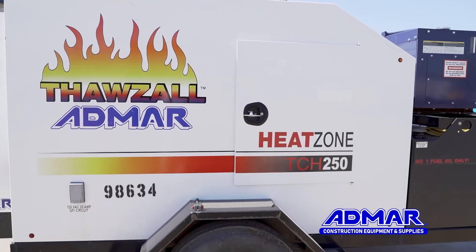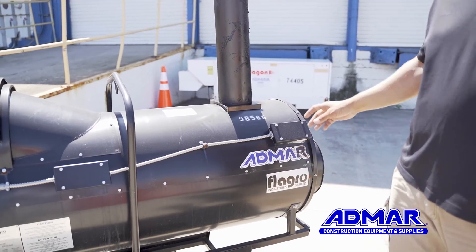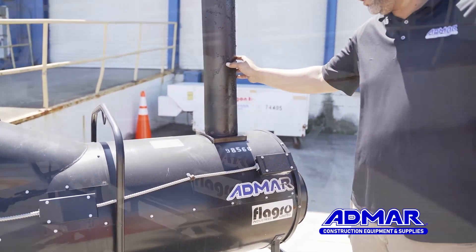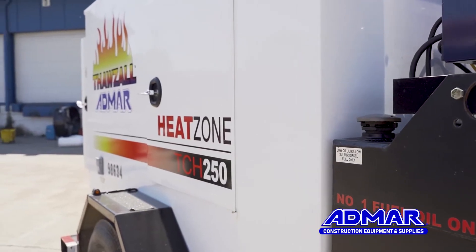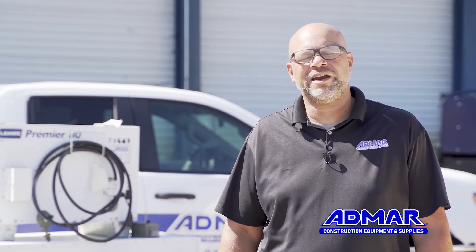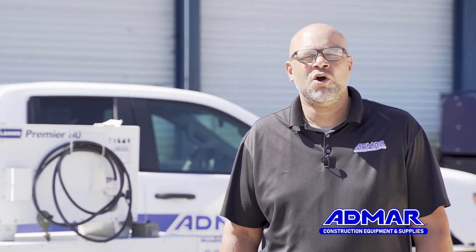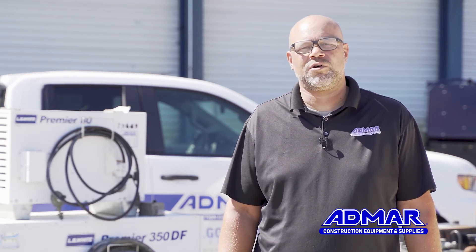The next type of heater we would like to discuss is the indirect fired heater. An indirect fired heater is similar to your home furnace. Temperature rise is achieved through the heat exchanger, and then this warm, clean, dry air is circulated into the project through a series of heating ducts. Although the indirect design lacks the 100% efficiency of the direct fired design, through the use of thermostats and placement of the heaters, they can be located outside of the project to assist with pressurization, or inside of the project to assist with recirculation of heated air. Your specific project parameters will dictate what the best piece of equipment is for your project.